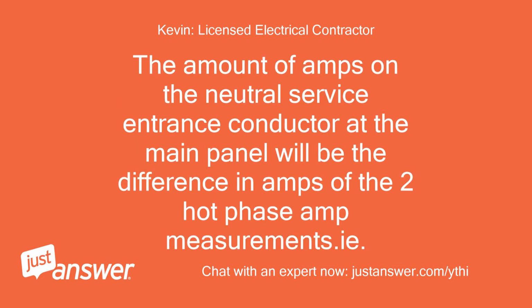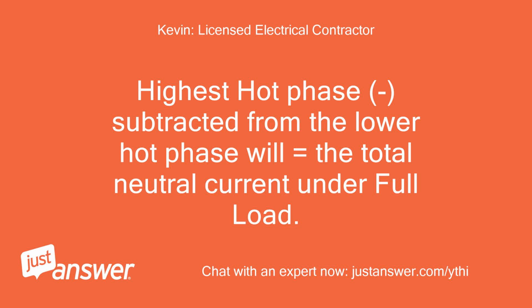The amount of amps on the neutral service entrance conductor at the main panel will be the difference in amps of the two hot phase amp measurements. I.e., the highest hot phase, subtracted from the lower hot phase, will equal the total neutral current under full load.